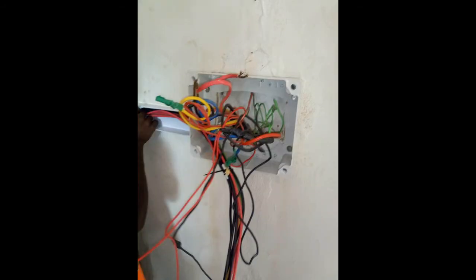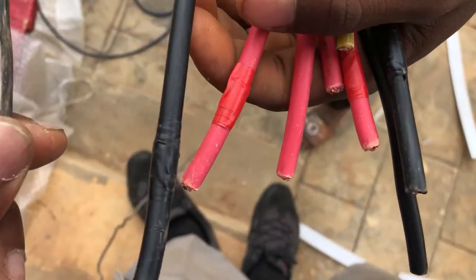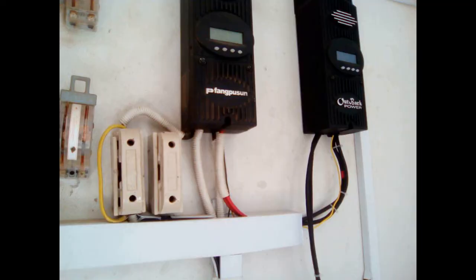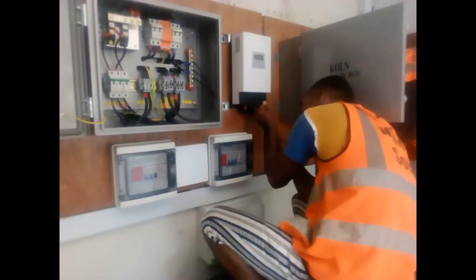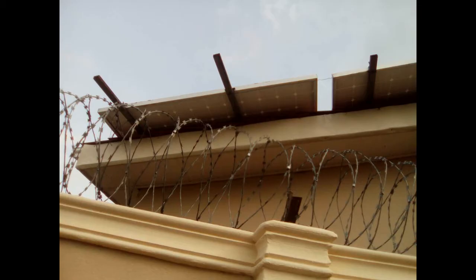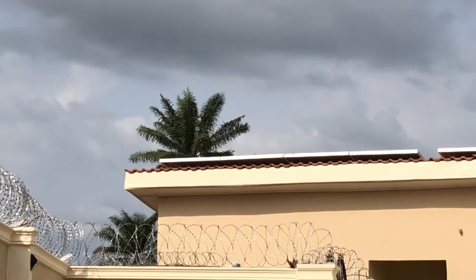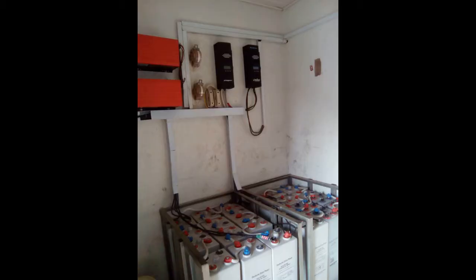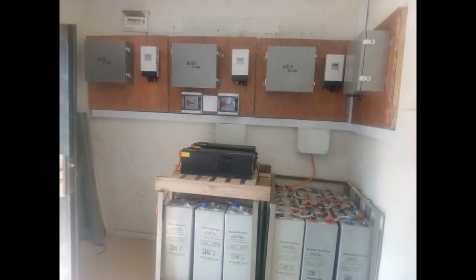So to recap, we've done the crazy wiring and sorted it out and put it in an electrical enclosure box. We've replaced 2.5 millimeter cabling criminally used on a 24 volt system with 10 millimeter electrical cables. We have taken off a system with no breakers or fusing and put proper interruptions in. We have gotten rid of the roof overhang, and it looks a lot better without the overhang. And just generally speaking, the whole power room now is a lot safer. It's got a proper design to it, lots of interruptions, lots of safety.